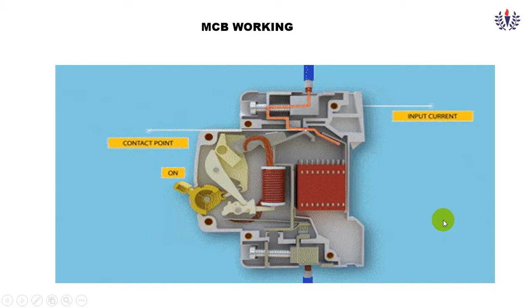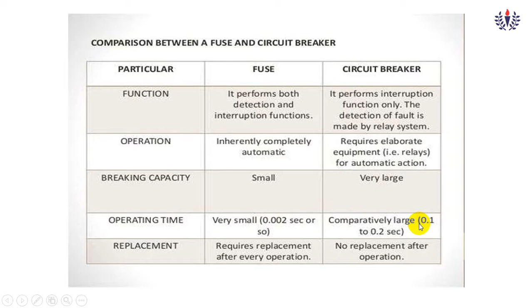So we want to see the comparison of a fuse and an MCB. So function, it performs both a detection and interruption function in case of fuse. In the circuit breaker, it performs interruption function only. The detection of the fault is made by the relay system, that is the magnet. Operation is inherently completely automatic. Here it requires a relay and automatic action also is required. Breaking capacity is small, low values of current, and here it is very large. Operating time is very small, that is 0.002 seconds. Here it is large. And replacement, the fuse requires frequent replacement, in the MCB no replacement is required.